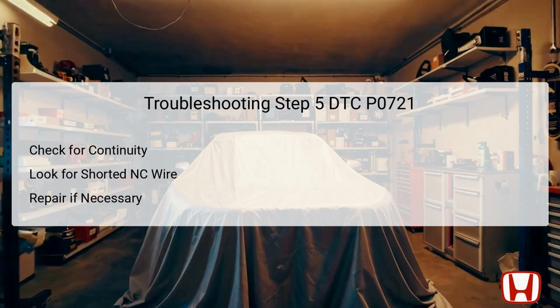If continuity is confirmed, it raises the possibility of a short to ground existing within the NC wire. If that is the case, repairs will be necessary to rectify any short circuits found before you can proceed to the next step. If there is no continuity and everything else is functioning correctly, it allows you to move forward in the troubleshooting process, confirming wiring integrity before proceeding further.